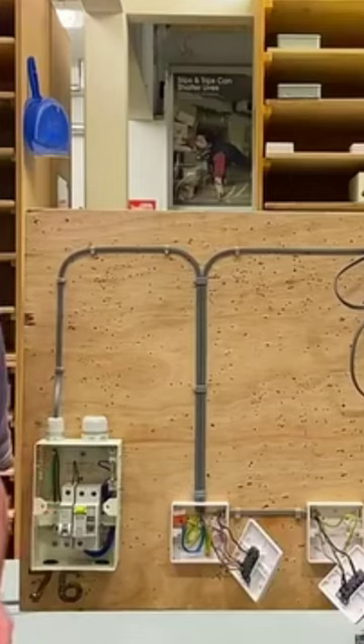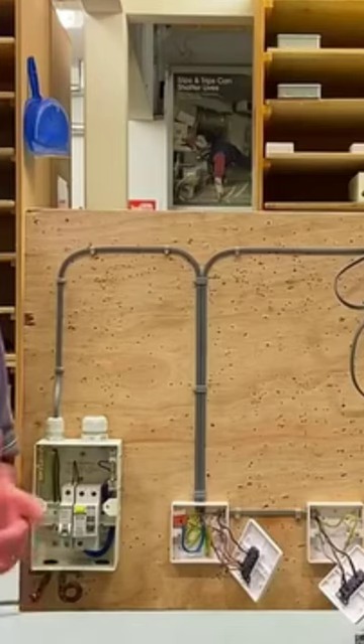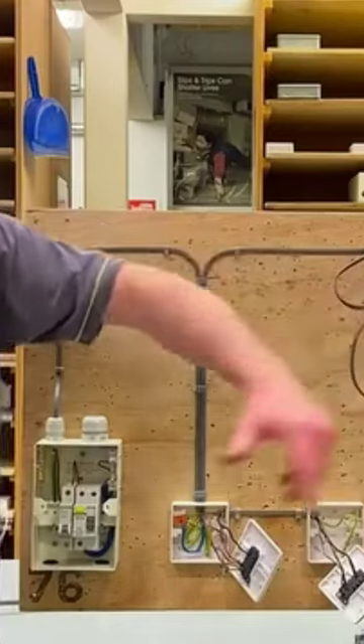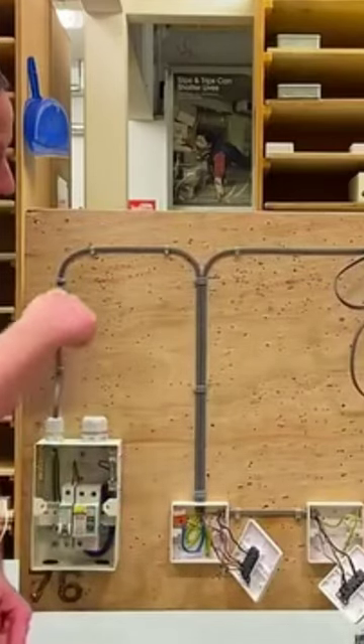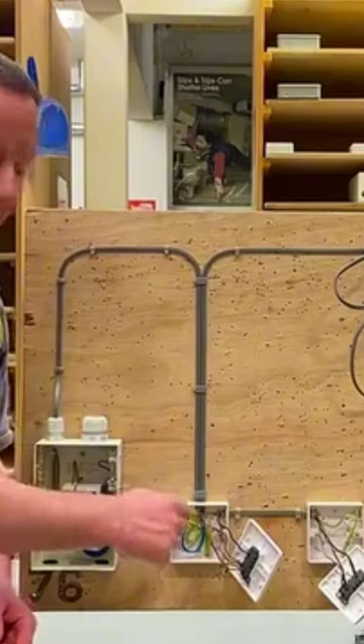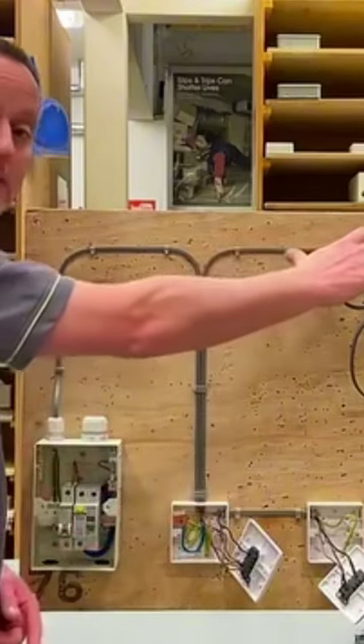We're going to continue in this video about the two plate method. We've looked in previous videos at a one-way lighting circuit controlling two LED downlighters using the two plate method, a method where the feed is taken directly to the light switch and the switching line and neutral goes out to the loads.